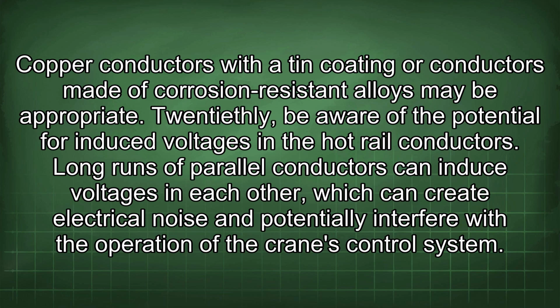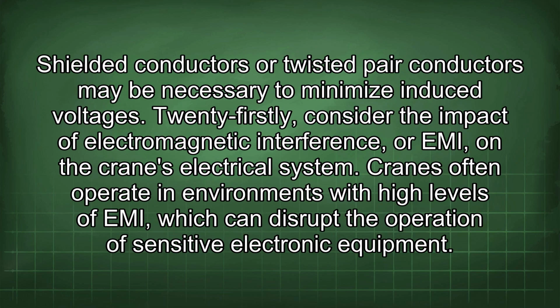20thly, be aware of the potential for induced voltages in the hot rail conductors. Long runs of parallel conductors can induce voltages in each other, which can create electrical noise and potentially interfere with the operation of the crane's control system. Shielded conductors or twisted pair conductors may be necessary to minimize induced voltages.